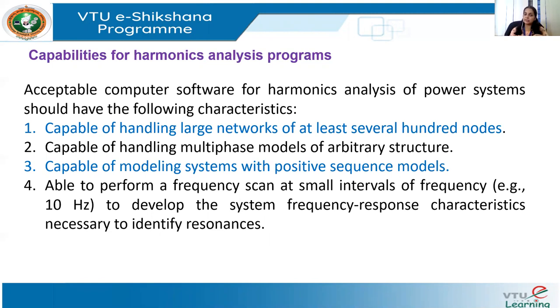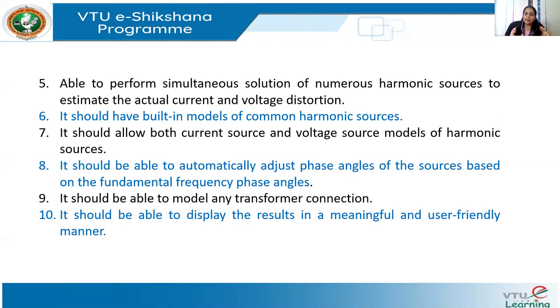The system should be capable of performing simultaneous simulation of multiple harmonic sources, since in a large system there can be many nonlinear loads present. It should be able to simultaneously model or simulate every harmonic source in the system and estimate the actual harmonic current and voltage distortion. This is another key requirement for any computer program used for harmonic analysis.